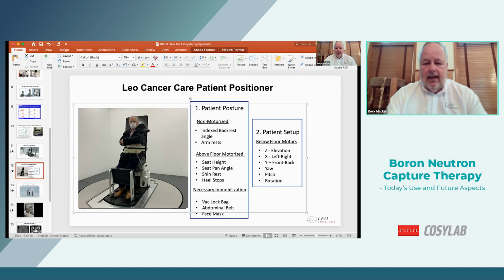Then the motorized shin rest moves into place, and immobilizing the knees and the shins really prevents the slouching that people worry about in upright radiotherapy. And then the patient is set up. The adjustment can be made with motors that are below the floor to provide elevation, left, right, front, back, yaw, pitch, and roll. So a 6-axis positioner to adjust the patient setup following imaging. And of course, imaging for a cone beam would be done rotating the patient.